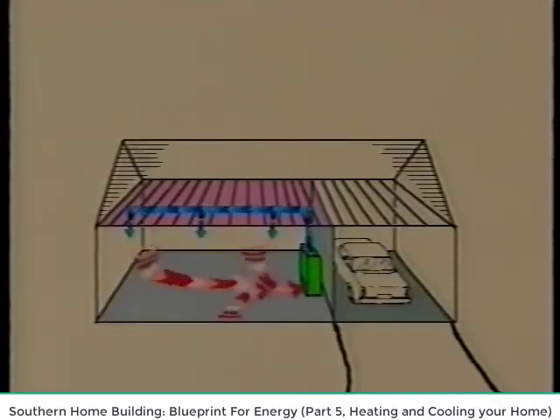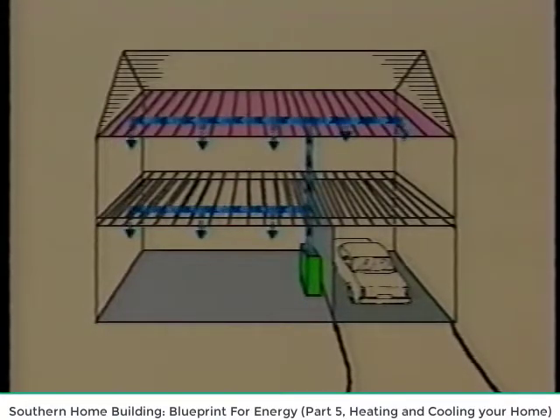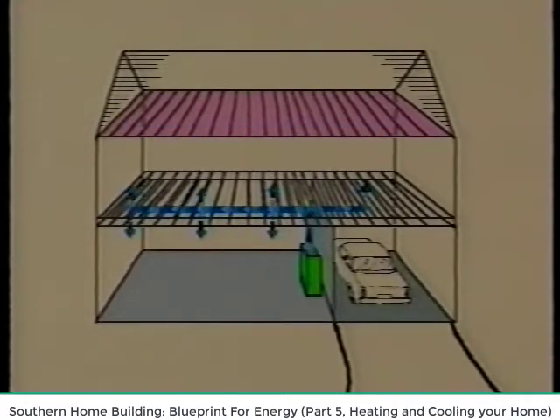It is not difficult to put the return duct and the air handler inside the conditioned space, but the real problem is, how can you get the supply duct out of the attic and into the conditioned space? For a multi-story house, it's relatively easy and less costly. No supply duct is used in the attic. The second floor receives supply air from the floor vents, and nothing changes on the first floor. With this method, approximately half of the total duct can be eliminated. Although the remaining duct has to be larger, significant savings result from reduced labor. In addition, potential energy losses resulting from the conditioned air leaking into the attic are eliminated.